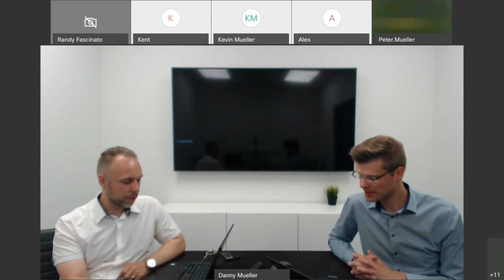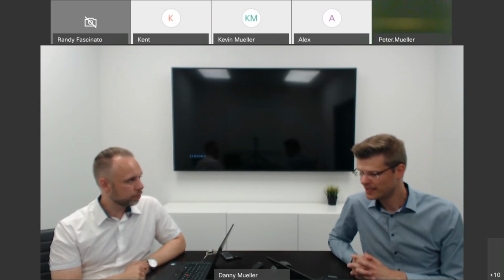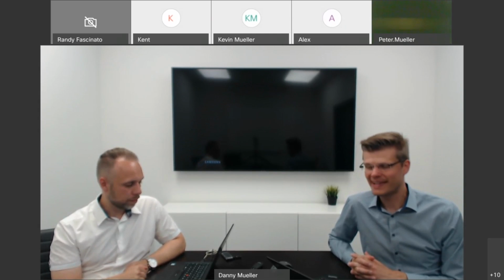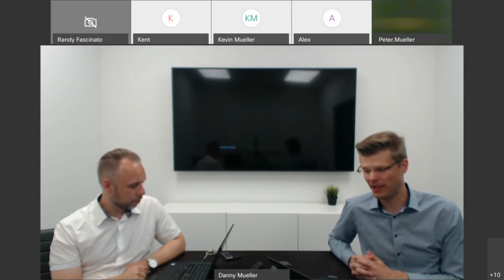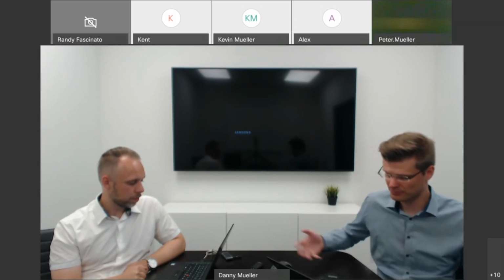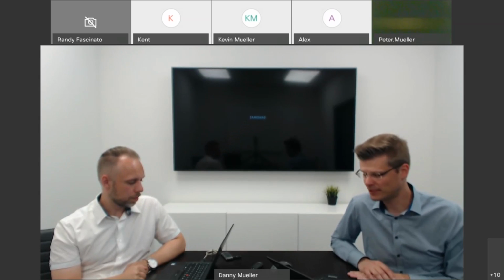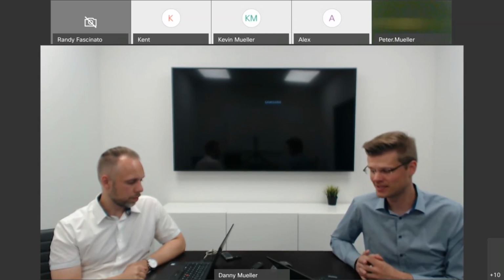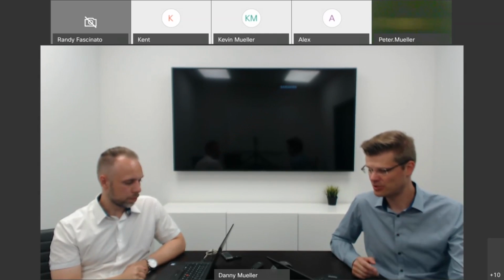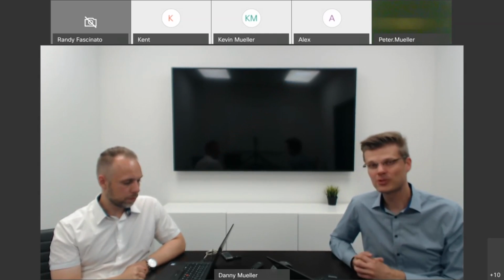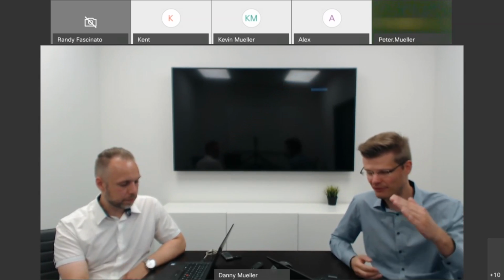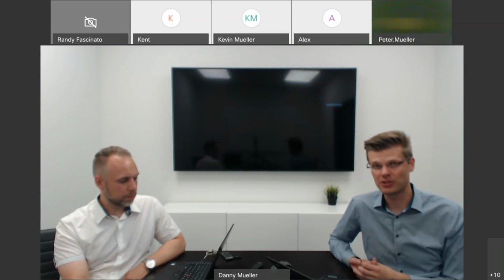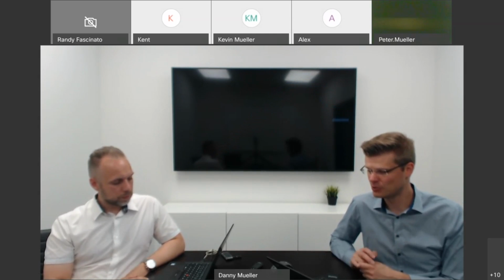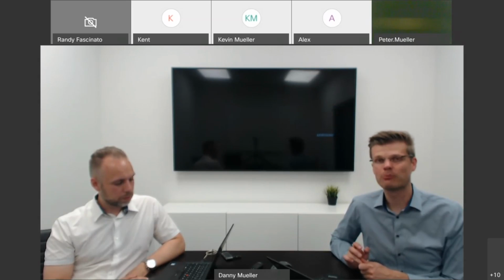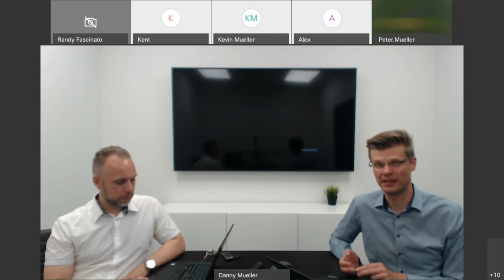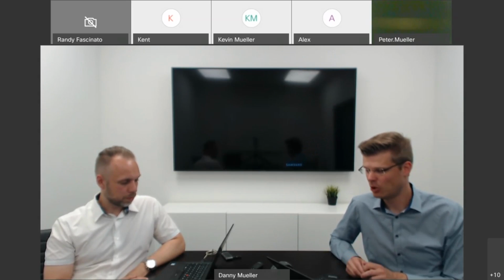Yunji asked about comments on bifacial module matching. So bifacial modules typically can have a higher output current depending on how much reflection you assume from your ground or from the structure beneath the panel being reflected to the backside. That's always a tricky question to ask. How much is that, and how much of that radiation will actually translate into more power from that backside? Most bifacial module manufacturers have a table where they say 5, 10, 15, 20%, whatever it is, bifacial gain, and you pick the gain which is appropriate to whatever you predict with your installation, and that will be the current which you will be using for determining if you can connect that to the inverter MPPT or not.